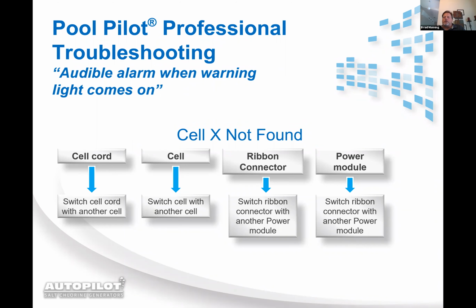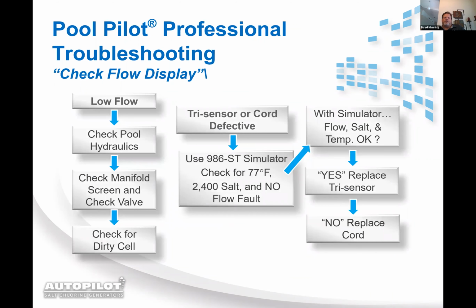Cells not found is one of the messages that will be displayed on the PoolPilot Professional. With cells not found, that could be a cell cord unplugged, or a burn-up at the terminal strip. That could be the incoming power to the power module, where the blue and brown wires bring the power module to 240 voltage, or the high voltage. They could be burned up. The display fuse could be burnt out. The power fuse could be burnt out, or there could be corrosion on the ribbon connector, or it could be a bad power module.